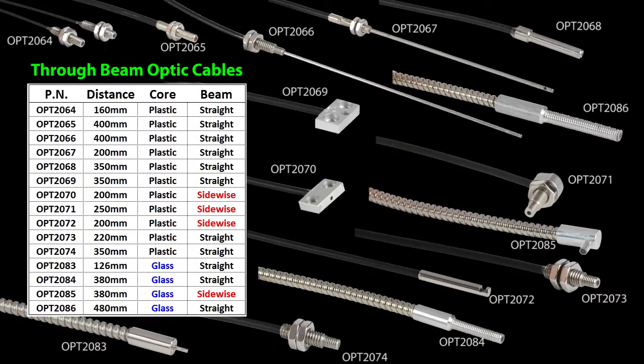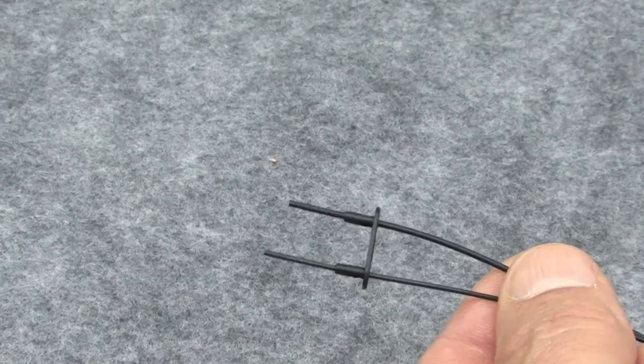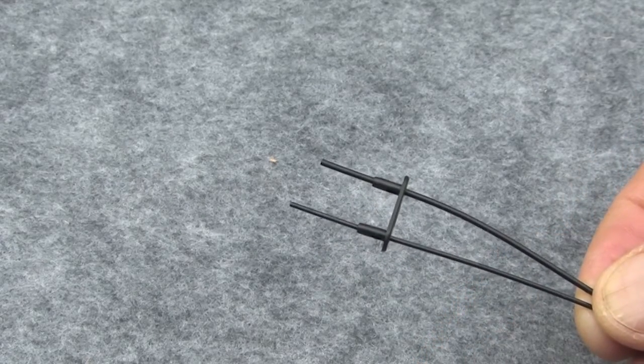The through beam OPT series optic cables, when used with the OPT series amplifiers, can be used out to about 19 inches. Some of the cables have a smaller diameter fiber core which gives you a tighter bending radius but also gives you a shorter detection distance because it collects less light.